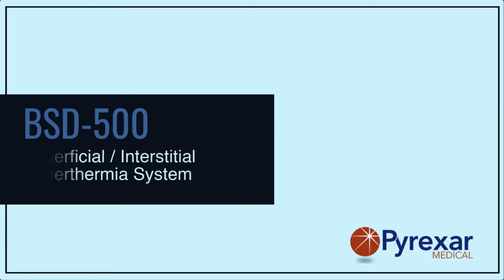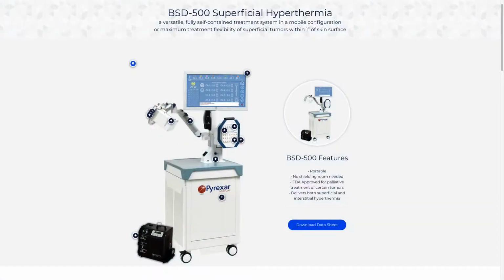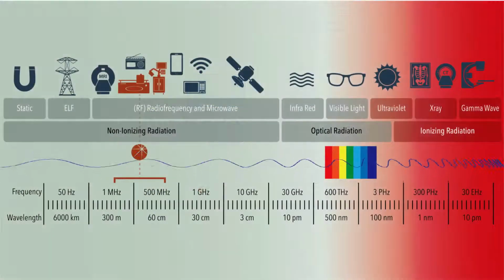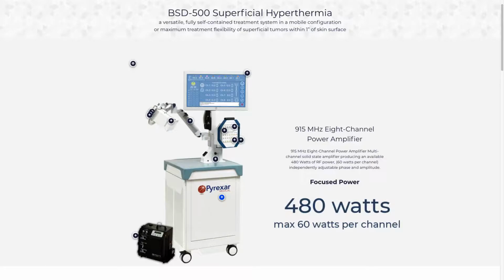Now I'd like to introduce the Pyrexar line of hyperthermia systems. The BSD-500 Superficial Interstitial Hyperthermia System. Superficial hyperthermia can treat solid tumors up to 4 centimeters from the skin surface. The system is portable, requires no room shielding, and is a Class 3 prescriptive device with U.S. FDA approval for palliative treatment of certain tumors, and can deliver both superficial and interstitial hyperthermia. The BSD-500 transmits RF energy at 915 MHz, generated by 8 multi-channel solid-state amplifiers producing an available 480 watts. Each channel is independently adjusted for phase and amplitude.